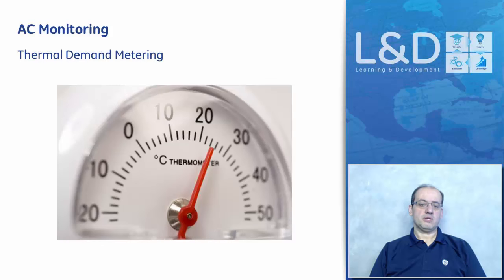TDM or thermal demand metering applications are used by utilities that require the ability to record power demand for calculating the equivalent of a thermal state of an electromechanical meter. The peak demand value is also calculated. So it's basically the thermal state and the peak thermal demand are calculated, stored in the concentrator for other applications that will pick up these values and do analysis on it.